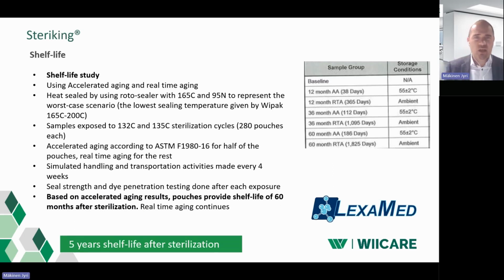Then shelf-life studies. Lexamed was using accelerated aging and real-time aging for this. They used the lowest sealing temperature and pressure that we give in our IFU for the materials, to represent the worst case scenario of this heat sealing, so that the seals will stay intact during the sterilization process. Then they did a huge amount of pouches and sterilized them in different sterilization cycles, and then part of the pouches after the sterilization was put into the accelerated aging process, and part into the real-time aging process. And after they were placed on the shelves, every 4 weeks Lexamed moves them to simulate the handling and transportation activities that are made in hospitals.